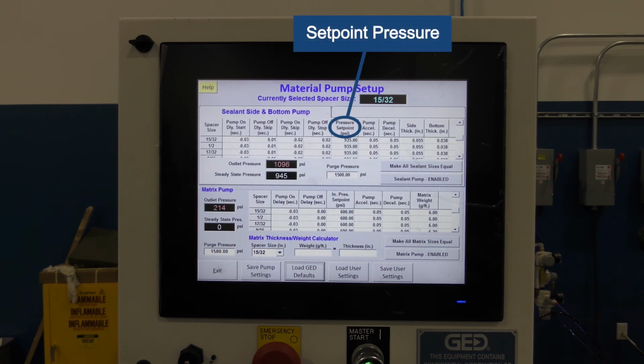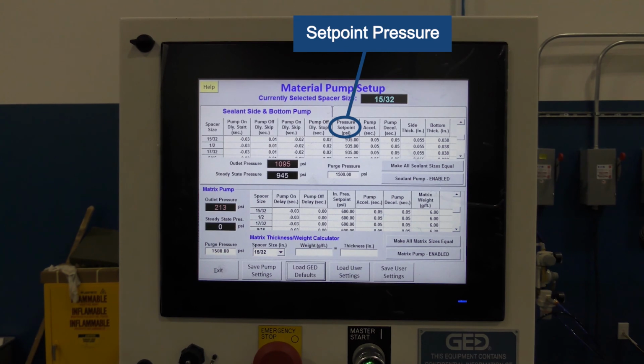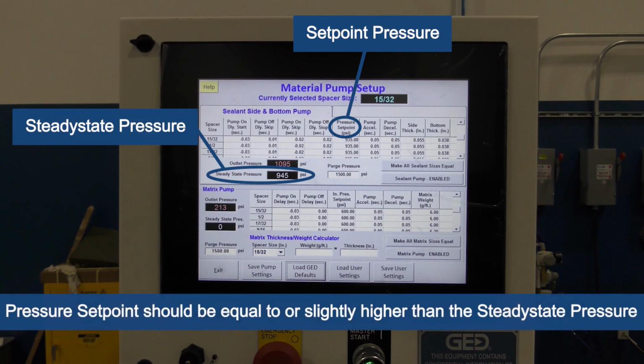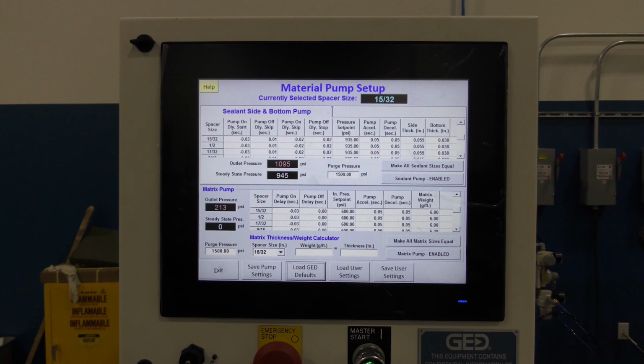You should also verify that the pressure set point for the sealant is acceptable. Typically, the pressure set point should be equal to or slightly higher than the steady state pressure. If necessary, change this value for the selected spacer size, make all sizes equal, and then save the pump settings. Back up your parameters.